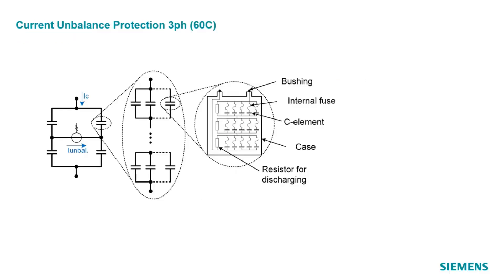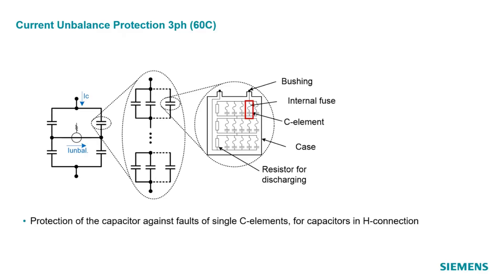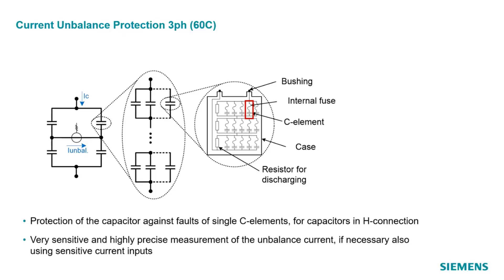The current unbalanced protection detects the failure of single capacitor elements in a cap bank. As shown in the picture, each of the four overall capacitors in the H-topology normally consists of several so-called cans in parallel and series, and each can is built up by a certain number of capacitor elements in parallel and series. The defect of a single element results in higher voltage that the other elements must cope with — additional stress for them. The more elements get broken, the higher the voltage for the remaining elements becomes, which is why all single element defects must be detected. The unbalanced current caused by a single defect is relatively small, so the function needs a very sensitive and highly precise measurement. If necessary, sensitive current inputs can be used.